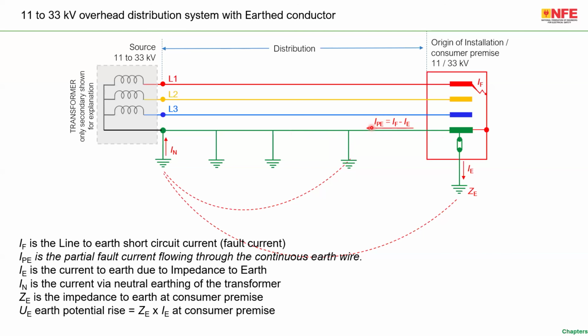A portion of the current will flow through the earth conductor IPE, and a portion of the current will flow through IE and ZE. So what I have put is IPE equals IF, meaning the total fault current, minus IE. So IF is the total fault current, IE goes to the earth electrode, IPE goes through the metallic fault return path. Now what you must calculate is the UE, the EPR at ZE, which is IE into ZE.